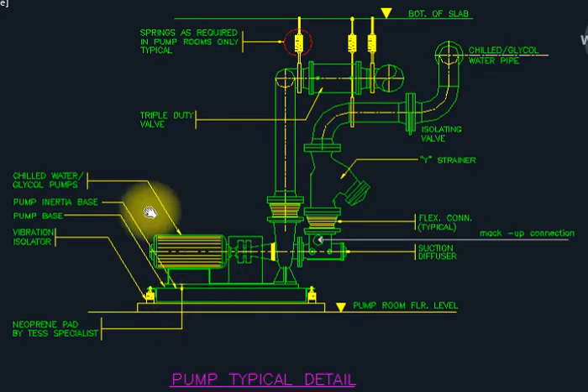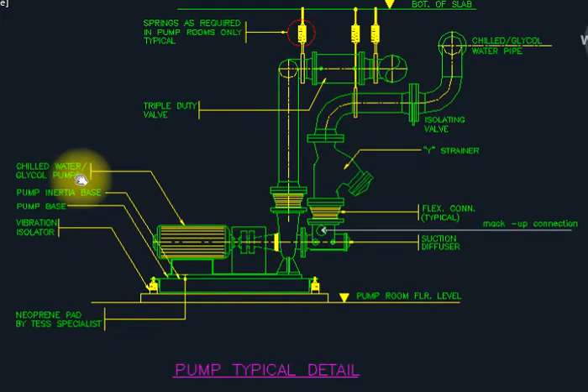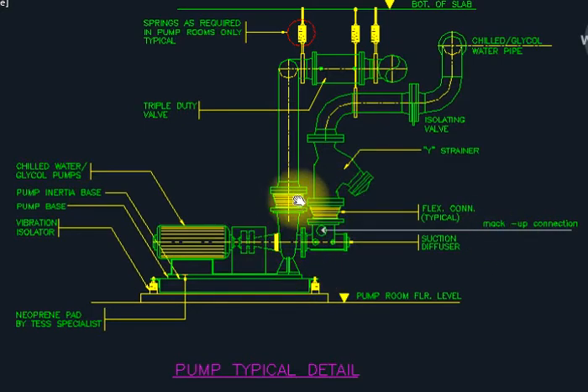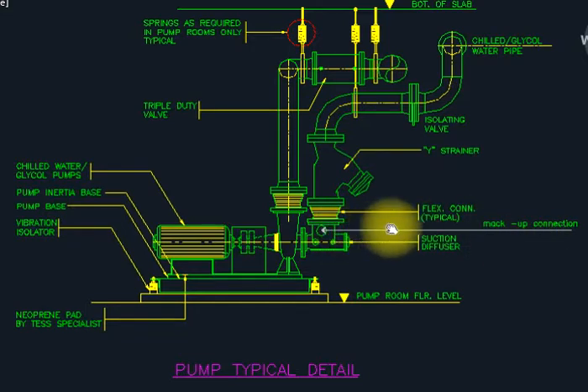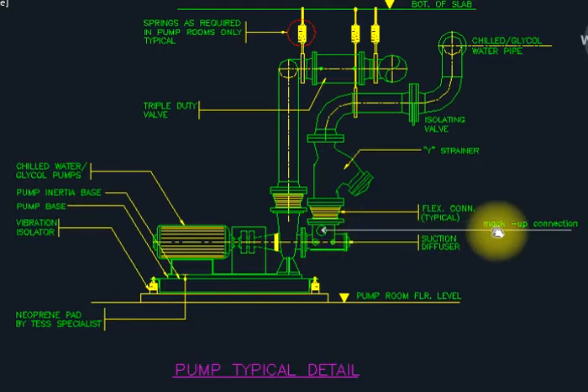This is the chilled water pump. And this is a makeup connection — makeup water is connected here. Because this is a closed loop, the chilled water pump works in a closed loop. Due to temperature changes or leakage, the water level may drop, so we have to make a makeup connection. The makeup water is potable water or simple domestic water connected as per the system requirement.